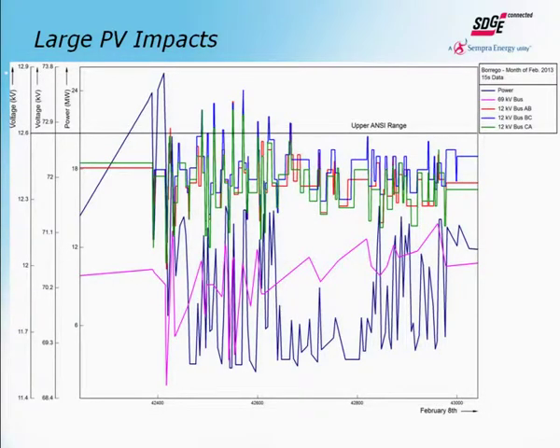If we zoom in here, you can see very rapid changes in a 26 megawatt array out in the desert. These are operational limits, and you can see we are actually in violation of those limits, with significant movement of our 12 kV bus.